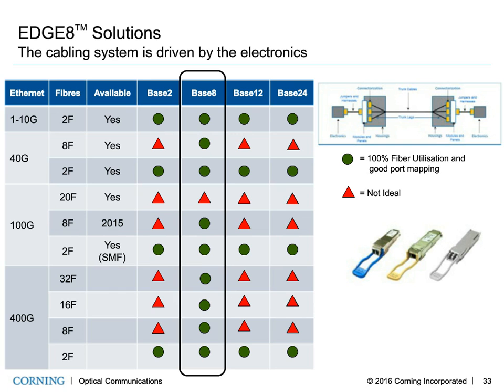So when you looked long term, what you really got to was the widely deployed solution for 10 gig, 40 gig, 100 gig, 400 gig. A Base-8 solution, since everything ended up at either increments of 2 fibers or 8 fibers, was an extremely cost-effective way. And for the first time, we're going to match the cabling infrastructure to the transceiver roadmap, right?